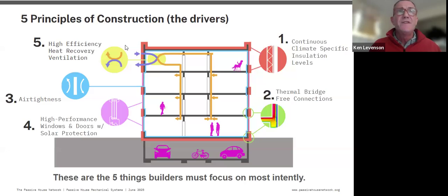The first four principles are all enclosure driven. The one mechanical system among the five principles is the ventilation, which we'll talk about at length. The ventilation will have high efficiency heat recovery, running 24/7, supplying fresh air continuously to the served spaces — bedrooms, offices, classrooms, living rooms — and exhausting from the service spaces — utilities, bathrooms, hallways — however you set it up, so you have complete ventilation.